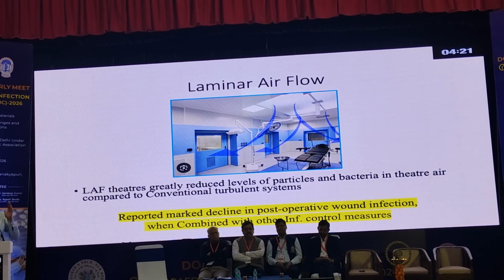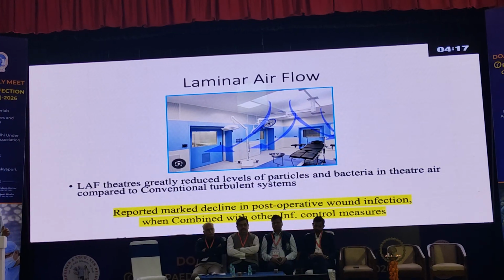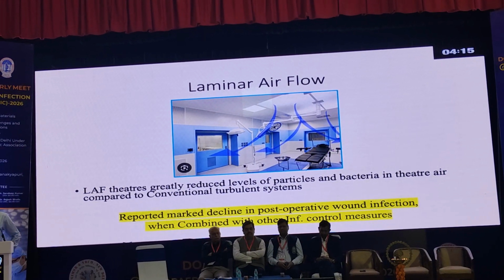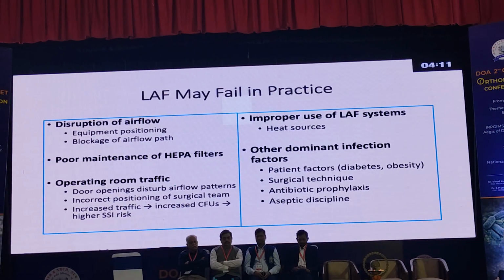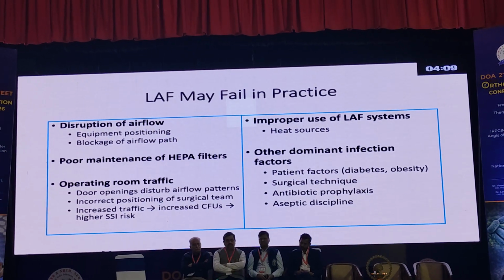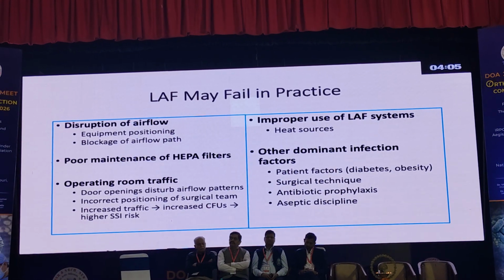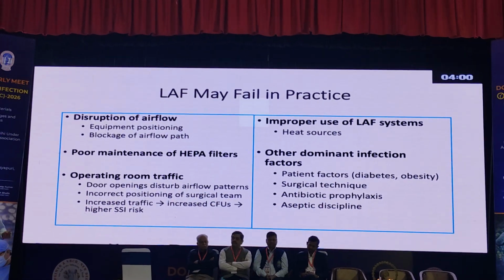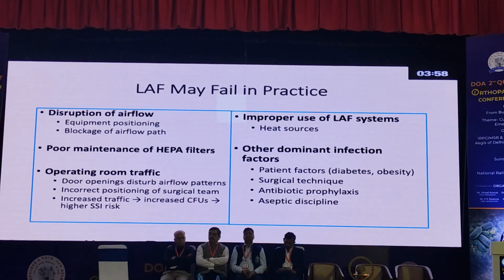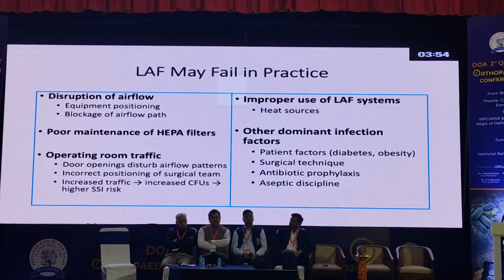With all other efforts for infection control, this has shown some improvement in the wound infection rates. But they can fail. You put in a laminar flow, but you block its inlets, it is not going to work. If the HEPA filter has not been maintained, it is not going to work. If there are heat sources around, again, it is not going to work. And if the patient has not been optimized, it's of no use.